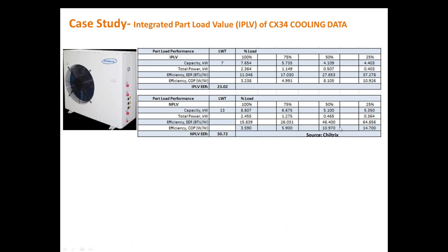As a case study, IPLV and NPLV are calculated for the Chilltrix CX-34 chiller model. At various loading conditions — 100, 75, 50, and 25 percent — they calculated capacity, total power, energy efficiency ratio, COP, and EER. The IPLV based on EER comes out to 23.02, and NPLV comes out to approximately 31. This is the type of data you will get from the manufacturer.